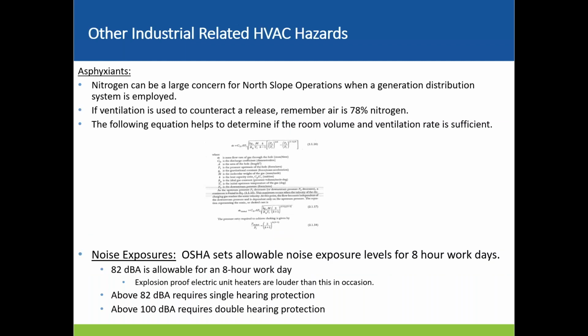And then just touch on some other industrial-related hazards to think about during your design if you're doing an HVAC project. Nitrogen was mentioned. Nitrogen can be a problem if we have a nitrogen generation system that's piped throughout a whole plant. To release your nitrogen, you're trying to fight it with air, and air is 78% nitrogen, so it takes a lot of air to keep it in the proper OSHA threshold for, I think it's 19.5% oxygen. And through the calculation you can use to determine that there. It's not a fun one, but we have a spreadsheet that does it for us now.